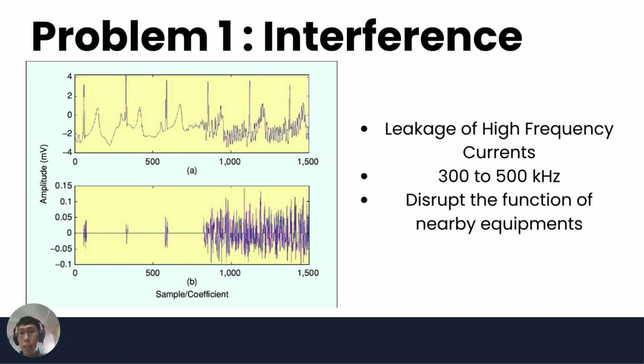They can disrupt the functioning of other equipment, primarily due to the leakage of high-frequency currents. The leakage of high-frequency current in the ESU is due to the 300 to 500 kHz output waveform utilized for its operation. This leakage occurs when the electromagnetic energy capacitively couples with specific metals present in the surgical environment. If the leakage surpasses a certain threshold, it can lead to interference with displays or other electronic circuits within the operating rooms. The most significant risk arises from the unintended current flow to both patients and staff, particularly when unintended capacitive coupling of high-frequency current occurs with metal objects near the surgical site.